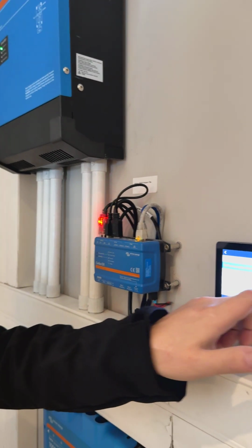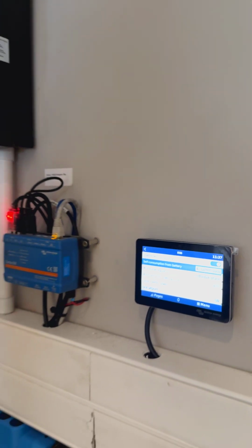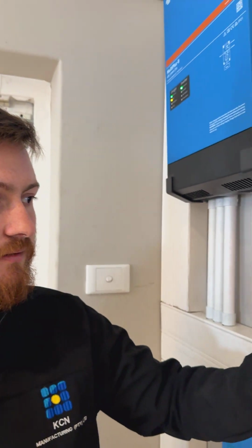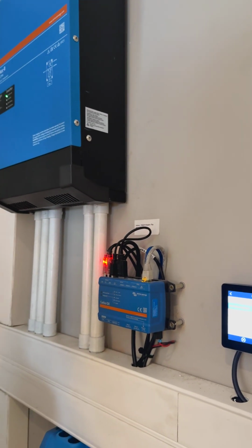Your multi-phase regulation setting applies if you have a 3-phase site that you want to set up on ESS control. In South Africa, due to our regulations, we are not allowed to feed back on one phase and pull on another phase, as we've discussed with our phase rotations on our energy meters. We are not allowed to do that within South Africa.